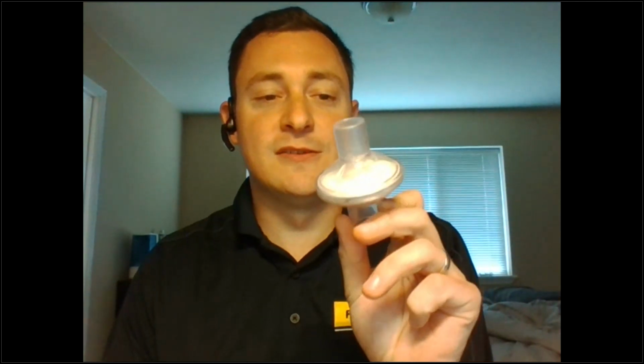So one thing I did note in the questions was there was one about keeping everything clean, keeping things disinfected. A big way to do that is extending the life of your gas flow analyzer by using filters and replacing them regularly. These aren't very expensive, but what it does is it keeps things out of your analyzer, out of the sensor, to make sure it keeps that accuracy for longer. Because we are dealing with a breathing circuit, we are dealing with patients, and there are things that we want to keep out of there. So this is another thing that's provided with the unit, but you do want to replace these regularly to get the best readings.